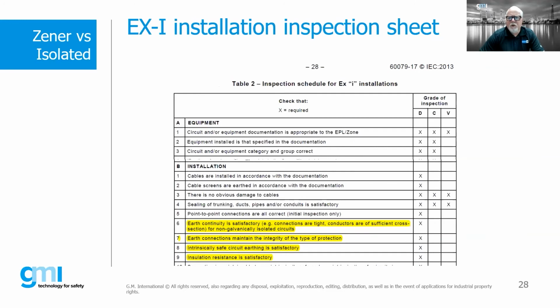So I threw this in here as well because some people ask, what do we actually have to do when we're doing inspections on EX installations, right? So this is actually part of what we call our initial detailed inspection. If you notice over here, this is out of the standard 60079-17 right here. So this grade of inspection, when you see a D, that means that's something that we need to be doing under what is called a detailed inspection. So if I'm building a skid package that involves, say, intrinsically safe barriers, these are the kinds of things that I need to check for, right?